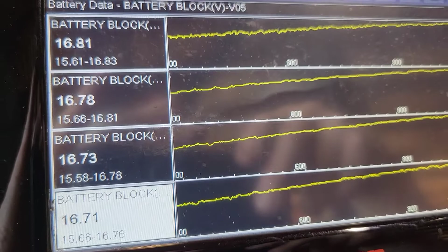From the time you started, it records the lowest battery voltage setting and the highest voltage setting for each battery block. In mine, I got really lucky because right off the bat, block 12 -- actually I had more than 12 blocks, I think, I can't remember, I didn't really look -- but block 12 was bad. It was all the way down to 13.5 or 13.7. I didn't write it down because it didn't matter, but all the rest were at 15 something. So that right there shows you that block 12 is bad.